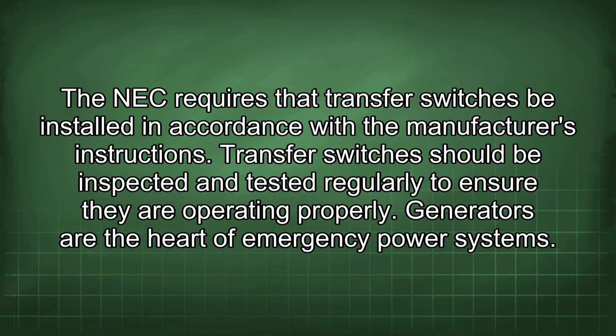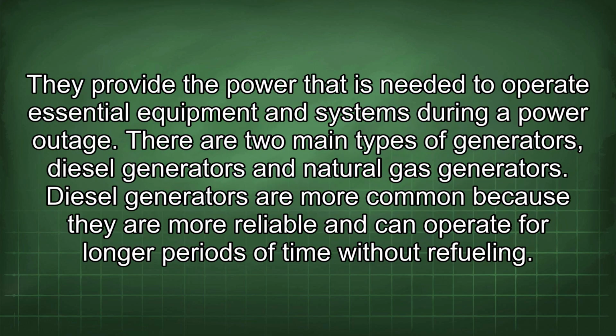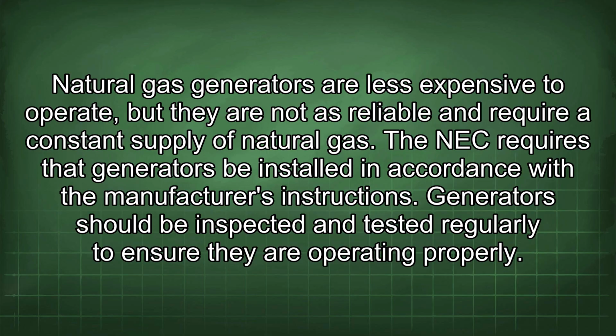Generators are the heart of emergency power systems. They provide the power that is needed to operate essential equipment and systems during a power outage. There are two main types of generators: diesel generators and natural gas generators. Diesel generators are more common because they are more reliable and can operate for longer periods of time without refueling. Natural gas generators are less expensive to operate, but they are not as reliable and require a constant supply of natural gas. The NEC requires that generators be installed in accordance with the manufacturer's instructions. Generators should be inspected and tested regularly to ensure they are operating properly.